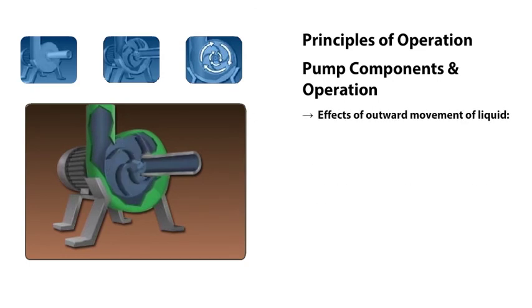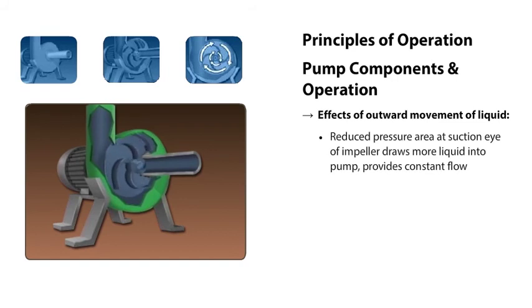The outward movement of the liquid causes two things to happen. First, it creates a reduced pressure area at the suction eye of the impeller. This area of lower pressure draws more liquid into the pump and provides a constant flow of liquid.